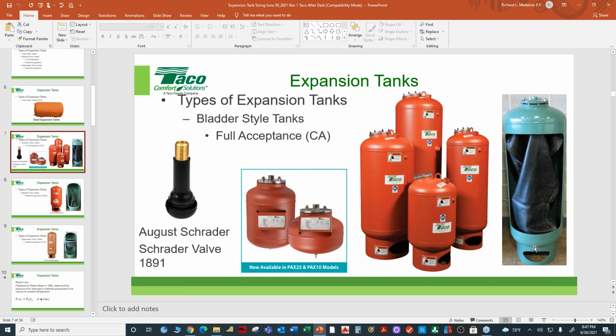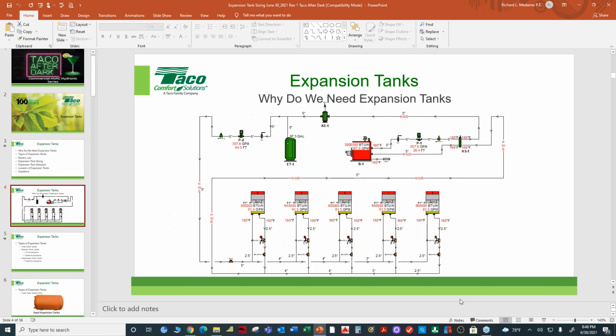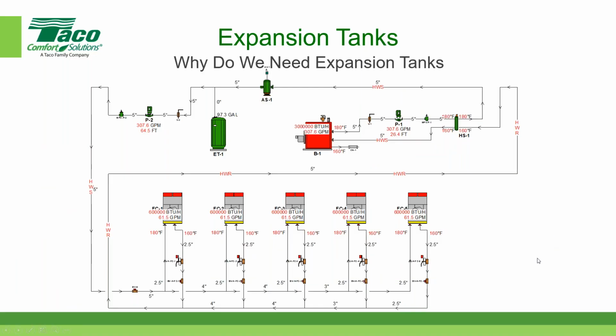Let's say the air that is dissolved in the water gets removed by the air and dirt separator, now the total volume of water in the system actually begins to contract. And so the bladder remains empty. As the fluid expands, then the water enters the tank. So it has nothing to do with the system flow. If we go back to our system diagram, it has nothing to do with the flow of the water in the system itself. Water enters and leaves the expansion tank at a very, very slow rate. It's a function of the expansion of the fluid.